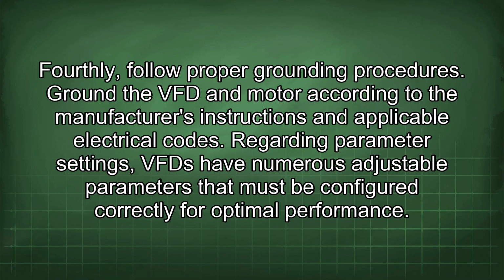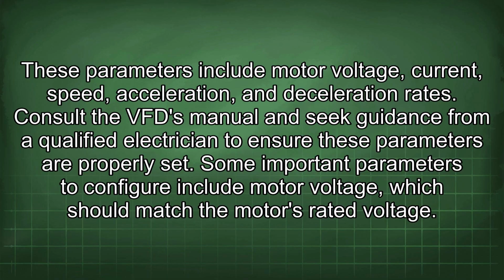Regarding parameter settings, VFD have numerous adjustable parameters that must be configured correctly for optimal performance. These parameters include motor voltage, current, speed, acceleration, and deceleration rates. Consult the VFD manual and seek guidance from a qualified electrician to ensure these parameters are properly set.